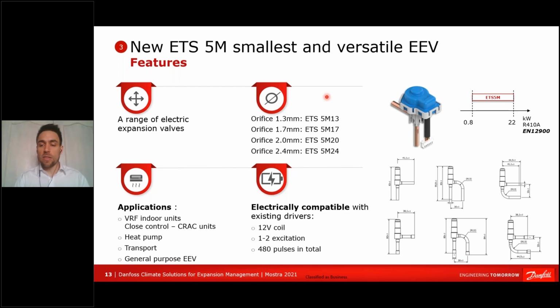It can go from 800 watts up to 22 kilowatts - I'm talking about R410A. It's a unipolar valve, so very simple to drive directly from your main controller - you don't even need a big driver to do that. Most controllers on the market today can drive unipolar valves. It has 480 pulses in total, giving you granularity and accuracy in how you open or close it.